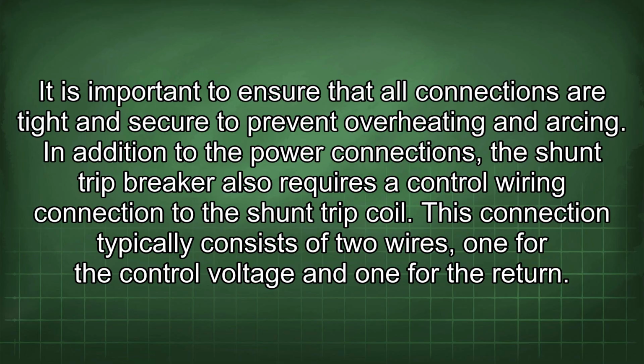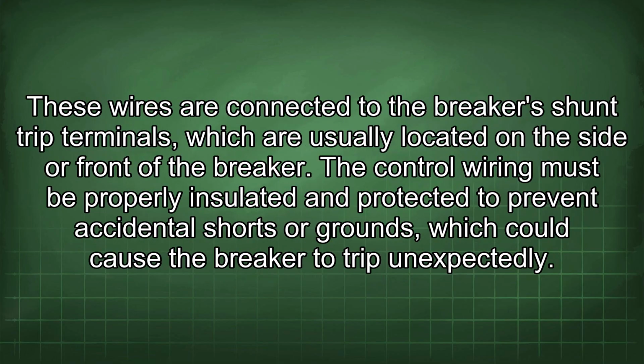In addition to the power connections, the shunt trip breaker also requires a control wiring connection to the shunt trip coil. This connection typically consists of two wires, one for the control voltage and one for the return. These wires are connected to the breaker's shunt trip terminals, which are usually located on the side or front of the breaker. The control wiring must be properly insulated and protected to prevent accidental shorts or grounds, which could cause the breaker to trip unexpectedly.